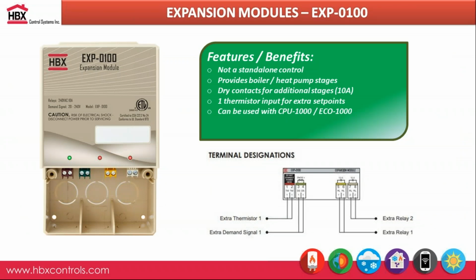What we have there is 2 extra dry contacts built into the unit, and these dry contacts could be used for pumps if you wanted to, but really it's more for adding stages. So you can keep adding 1 expansion, 2 or 3, to a maximum of 6 expansion modules with the EXP100, for a total of 14. The first stages, 1 and 2, are always going to be off the controller, but for that first EXP100, it's going to be stage 3 and 4, and so on as you keep adding more expansion modules.